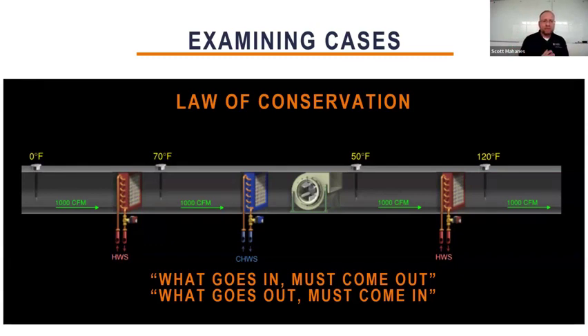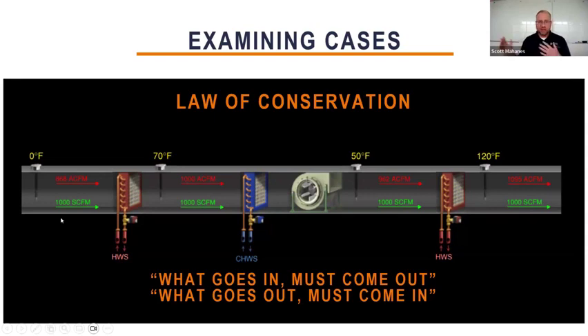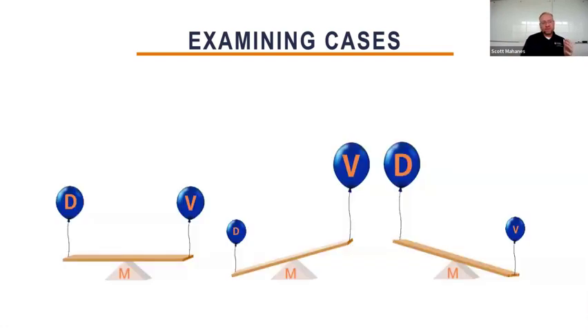In reality, the law of conservation has nothing to do with volume and everything to do with mass. And so I'm going to change these numbers slightly, which shows you that if you have a standard CFM value measured over here on this side, it is the same across the board. Mass flow is the same, but if you look in red at the volumetric flow rates, they're very different. At every stage, every different density airstream, it's a different volume. It's crazy. Now, what's really happening here? Well, mass dictates what's really happening: mass flow.